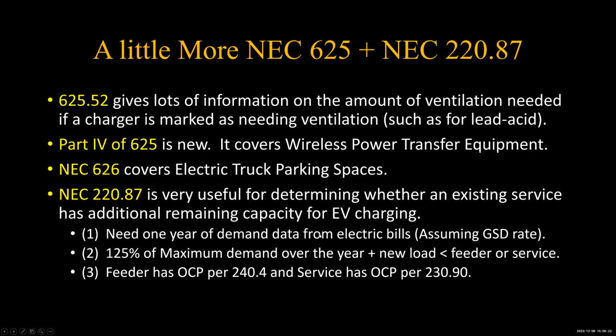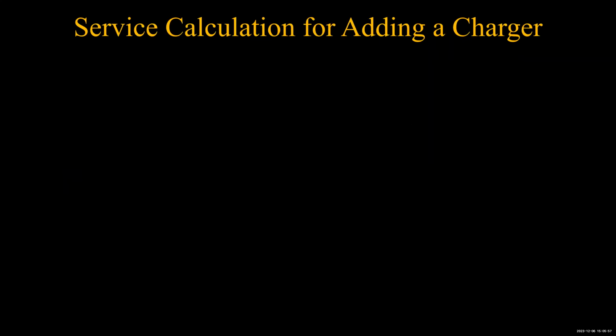I've done one condo that had a 1,200 amp service, and their largest demand over the year was 300 amps. That's 900 amps left over for charging electric vehicles. Well, not really. 80% of that 900 amps is available if you look at the 125% rule. All right, so these are the rules, and this 220.87 along with 625.41 is what it's all about. So keep those two in mind, and let's do some calculations.